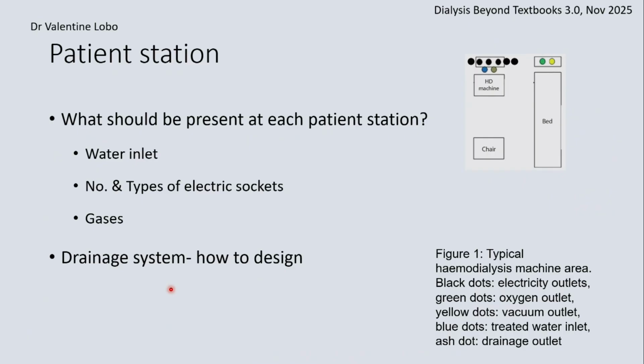It will also depend on the geographic location of your ICU from your renal unit. If they are on the same floor, just adjacent, engineering principles will allow you. If too many bends are introduced by giving that branch, then it may not be worthwhile. One, because of stagnation, and the second is because your transfer pump may not have the capacity to deliver the flow and pressure required at the end of the line. So sometimes it is better to have a dedicated system for that. When we put in here, we have 4 systems, one for each of them, simply because the configuration of the buildings didn't allow a pipe to be taken.